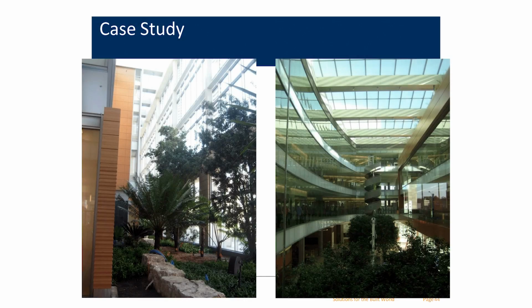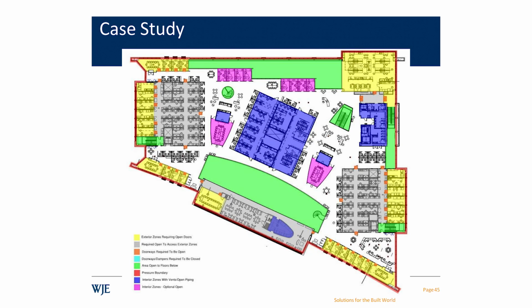One thing that helped us out on that testing is that this building had some significant full height atria. So 2 very, very large atriums that allowed us to provide a single zone for the entire test. So one of the efforts up front was identifying the pressure boundary. We need to calculate the surface area of the enclosure, and as Fiona talked about, those usually aren't just 6 sides. We have ins and outs and ups and downs and all over the place. So calculating the surface area of an enclosure can be a significant undertaking here. And then we also have to identify which doors need to be open, which doors should be closed, which dampers need to be taped off.